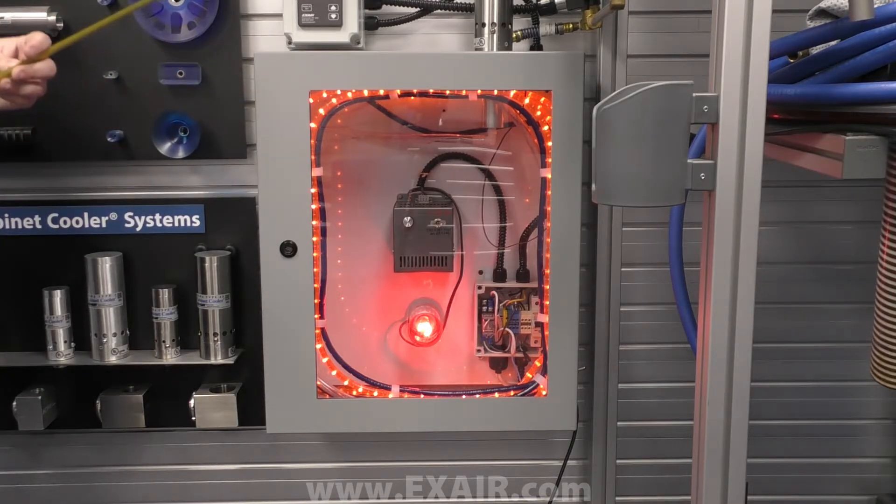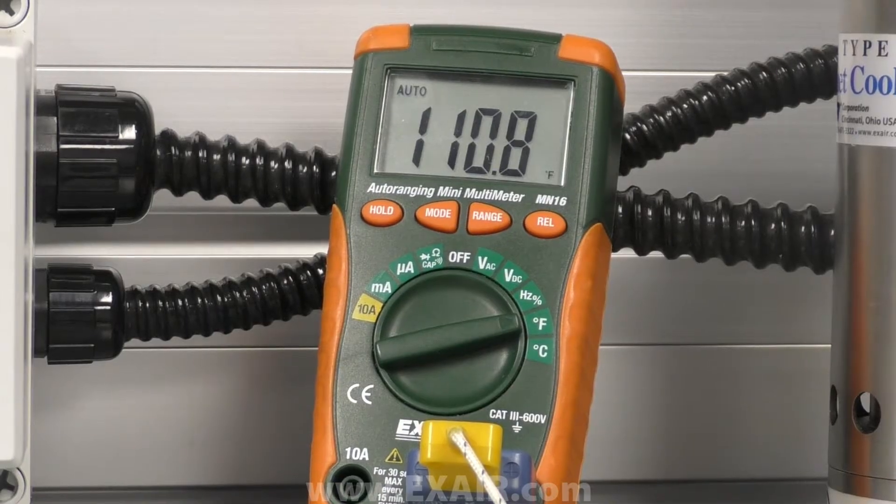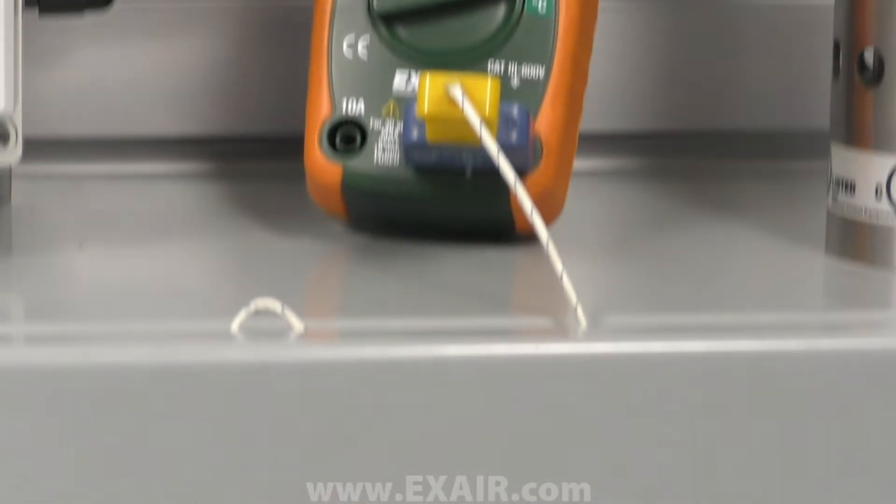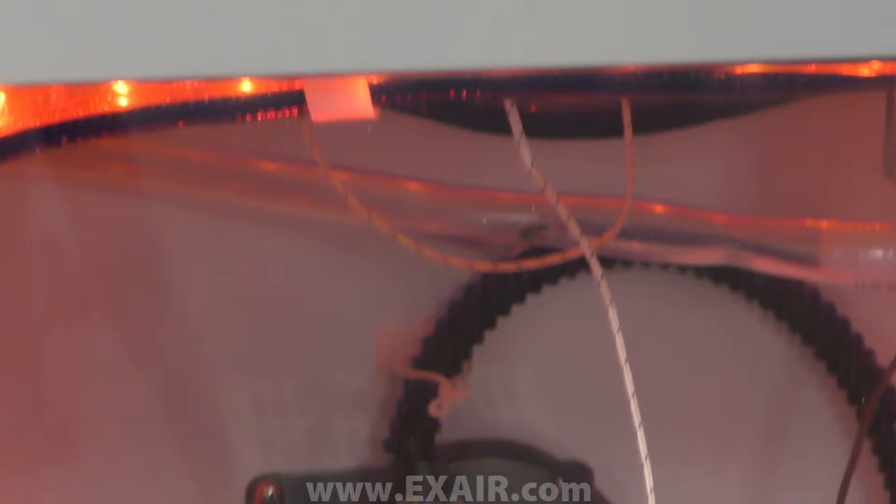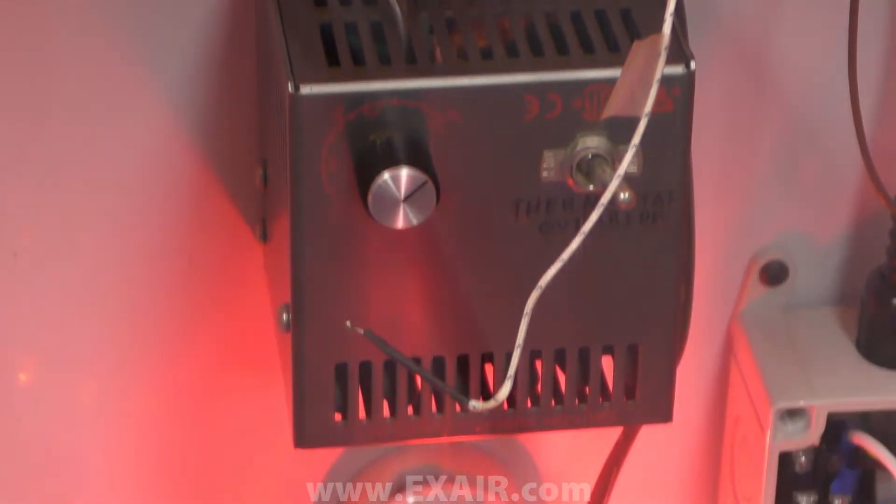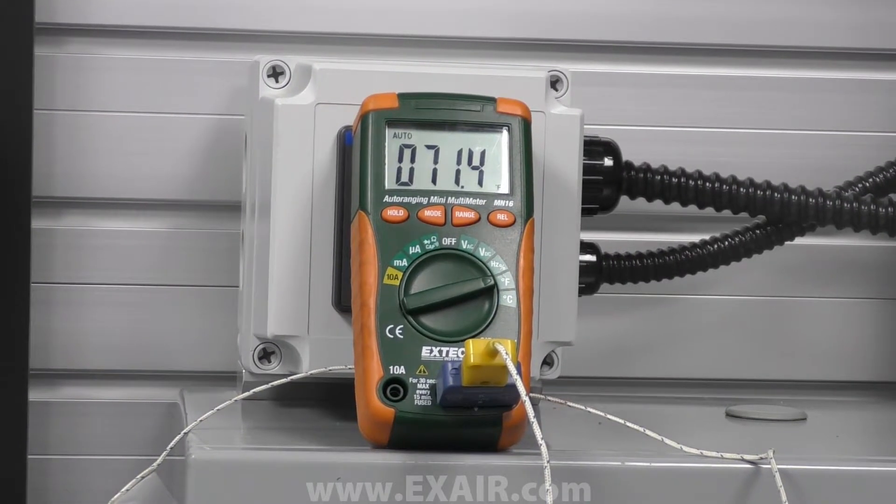Now we need the current internal air temperature and the current external air temperature. Be sure to use a thermometer to measure the air temperature and not an IR gun as those measure surface temps. In this video, I'm going to be using a J style thermocouple.